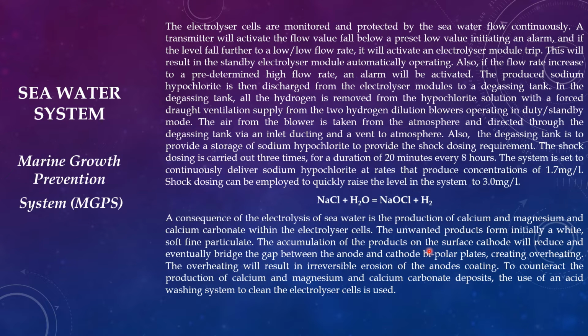The accumulation of these products on the cathode surface will reduce and eventually bridge the gap between the anode and cathode bipolar plates, creating overheating. The overheating will result in irreversible erosion of the anode's coating. To counteract the production of calcium and magnesium and calcium carbonate deposits, an acid washing system is used to clean the electrolyte cell.